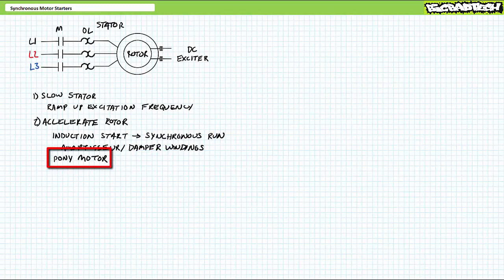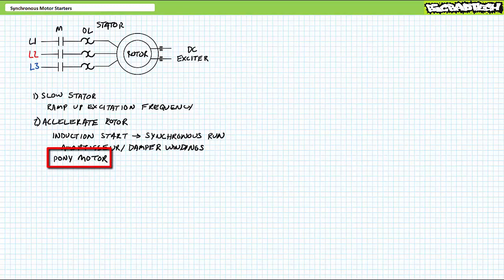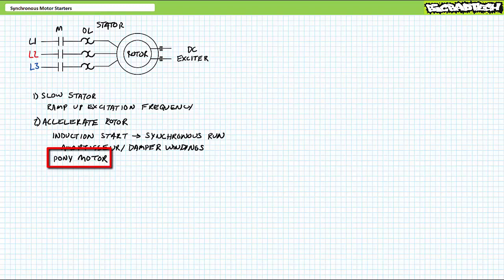Moving on. Another popular method commonly used to start a synchronous motor is to, believe it or not, use another motor or mechanical means like a gas-powered engine, a hydraulic motor, or even a domestic animal to accelerate an unloaded rotor to near-synchronous speed before turning on the exciter. You think I'm joking about the animals, but I'm not. This method is called a pony motor for valid historical reasons. A pony motor is essentially a small motor used to simply get the rotor turning, not to do any actual work.